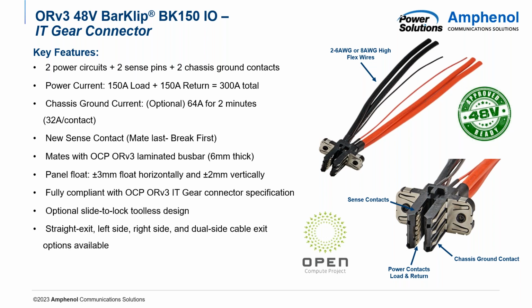The next change is we've added new sense contacts for mate last, break first capability or hot swap capability. This is to be used in conjunction with the hot swap technology within your system to avoid any damage when unmating from the bus bar or damage to the contacts. The last change we've made is we've added some additional float capability on the horizontal axis to plus or minus 3 millimeters versus the 2 millimeters that we've had on the ORV2 spec.